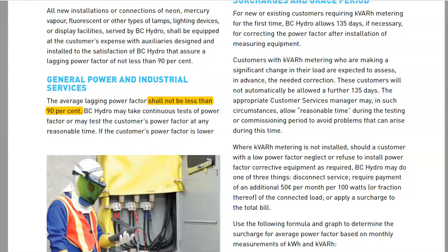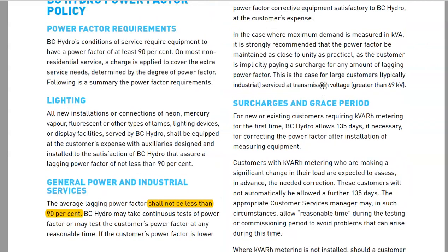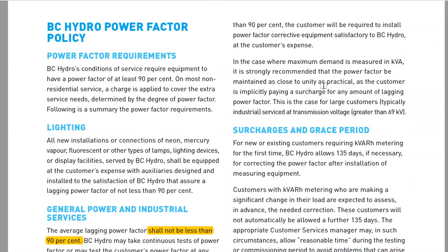sentence. The average lagging power factor should not be less than 90%. And underneath that, it says BC Hydro may take continuous tests of power factor. That's what they're doing now with these electronic meters. Or may test the customer's power factor at any reasonable time.